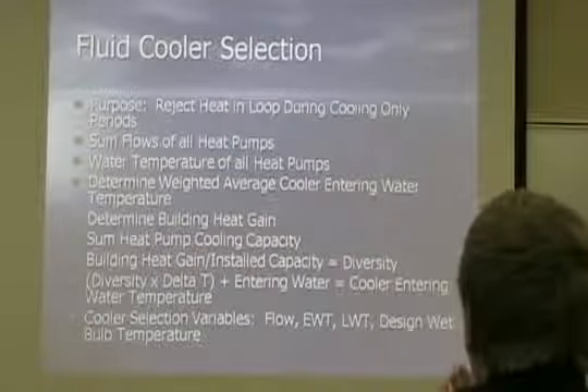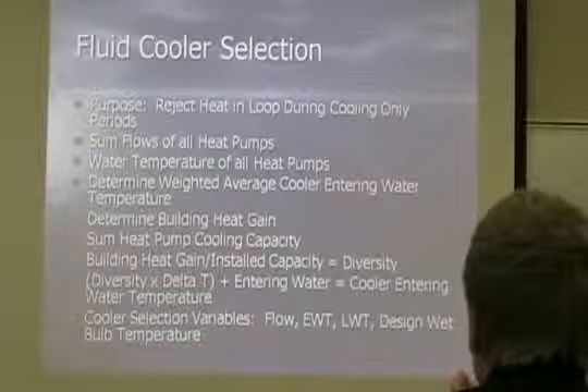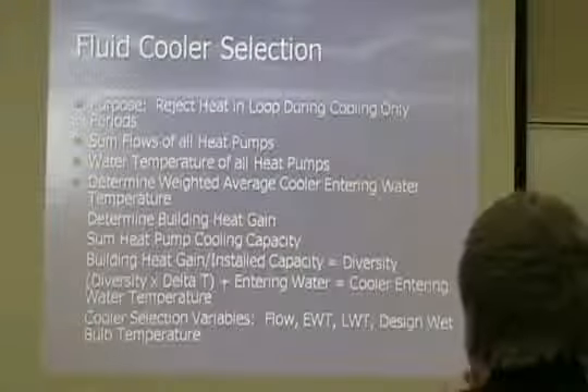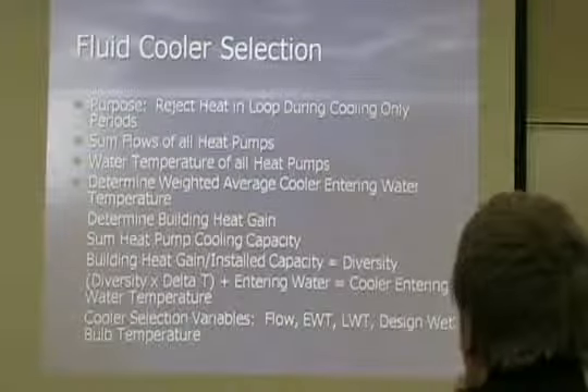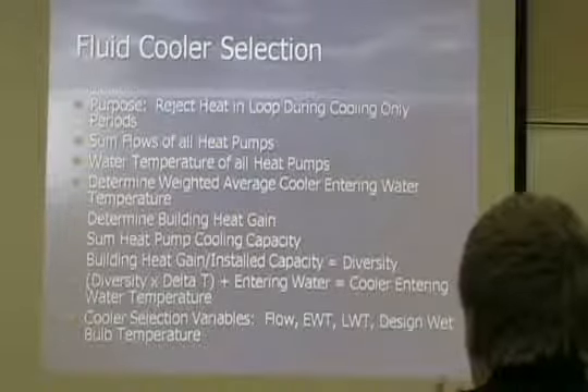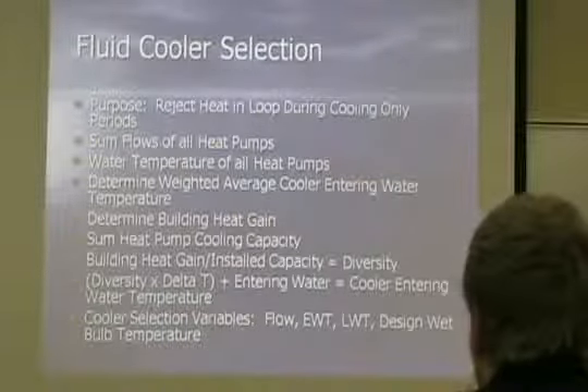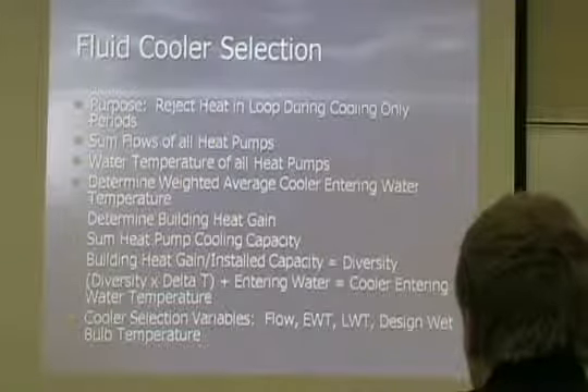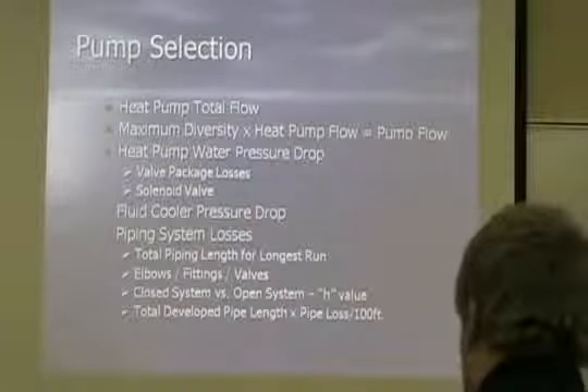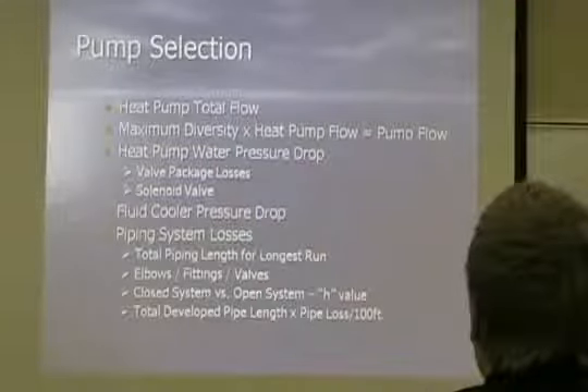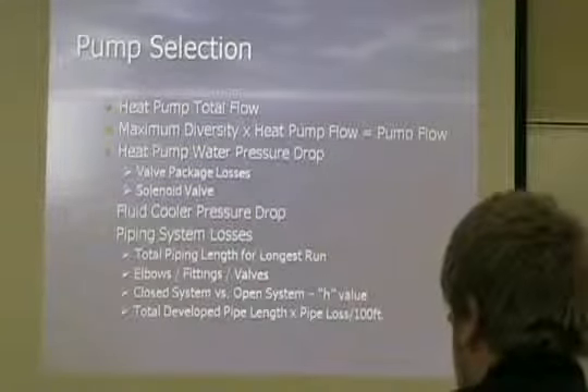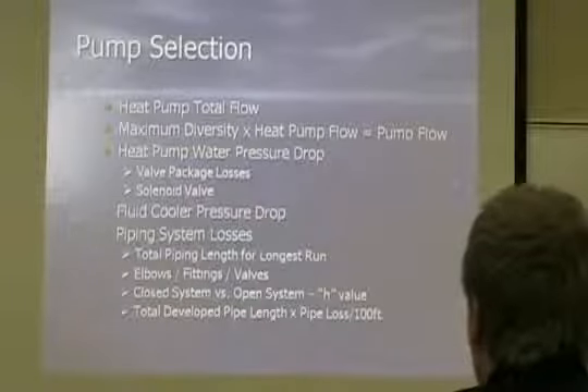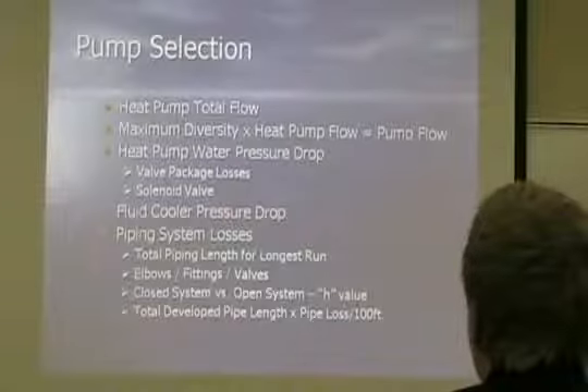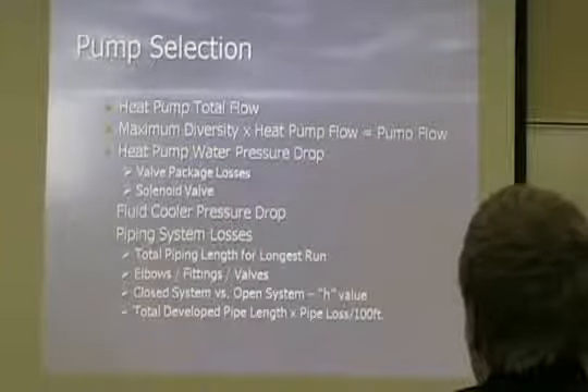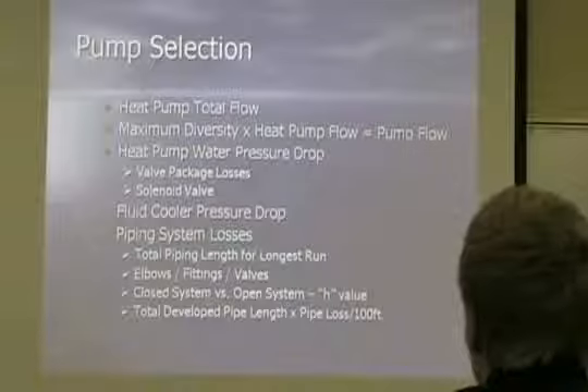The fluid cooler selection, again, the purpose of the fluid cooler is to reject the heat from the loop. In the cooling mode, all my compressors are on, I'm rejecting heat to that water loop, so my water temperature is going up in the building. So I've got to have a means and method to reject the heat from the building. Again, there's ways to size that fluid cooler. Pump selection is just like any other building. We take your total flow, take your maximum diversity times the heat pump flows equals the pump flow. So again, you don't necessarily have to take the connected load of all these units. You can consider diversity in some design methods.